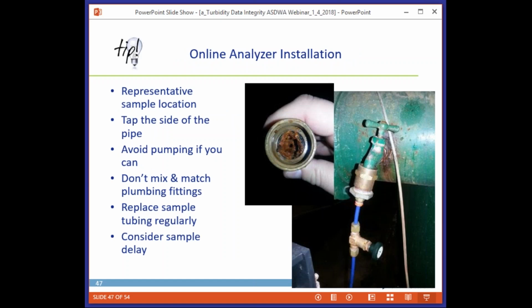So some tips here, looking at the online analyzer installation. We want to get a representative sample location. There's a lot of things affecting data integrity. We're looking for turbidity in this case to represent filtration performance primarily, not filtration plus additional settling or clarification occurring, say, downstream of the filters after the clear well. So the location that we pick is a significant issue.